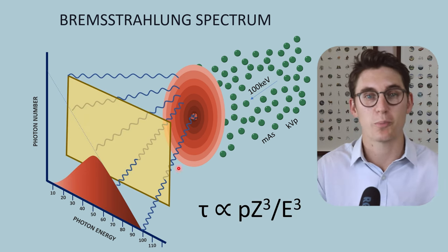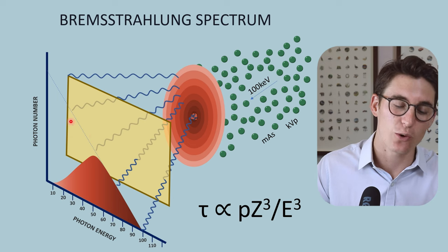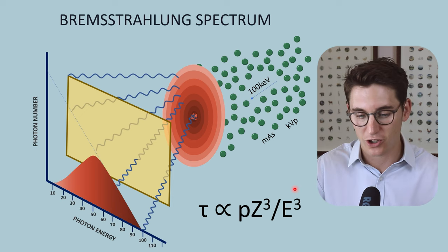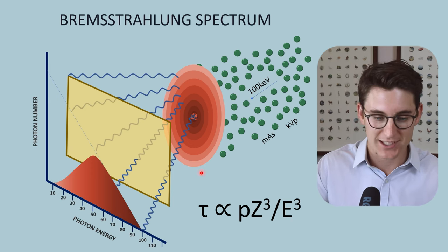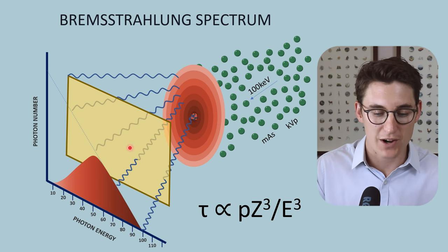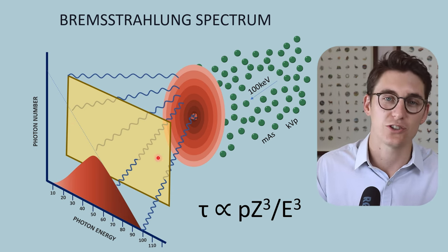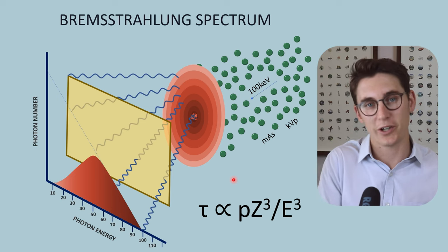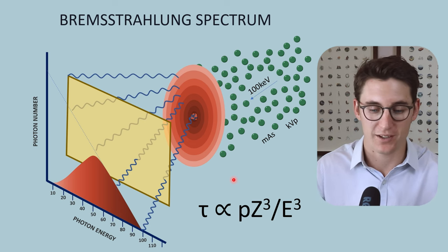If we place a filter between our target material and our patient, we preferentially filter out these lower energy x-rays — those that contribute to patient dose but don't contribute to our image. This occurs via the photoelectric effect. As the energy of x-rays increases, the likelihood of the photoelectric effect decreases, so we preferentially attenuate lower energy x-rays and higher energy x-rays are more likely to pass through the filtered material. This filter can represent our inherent filtration — the glass envelope, conducting oil, and x-ray tube window — or the added filtration placed between the x-ray tube and our patient.